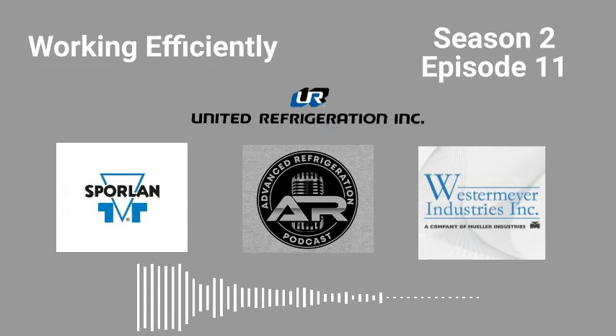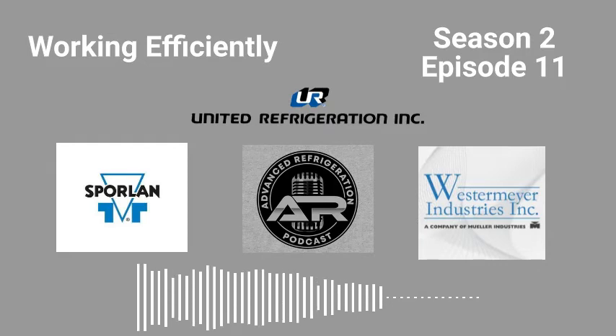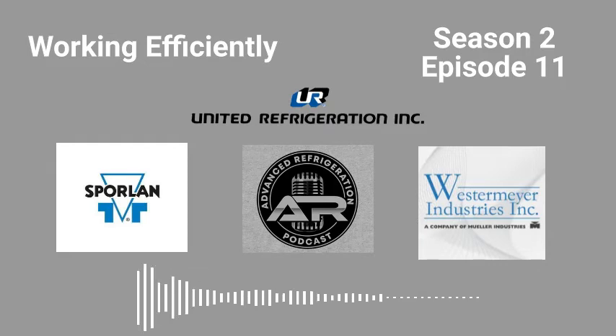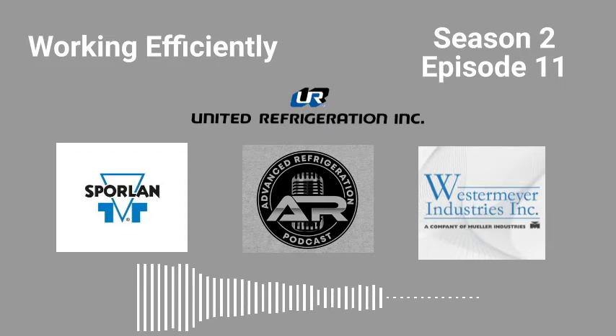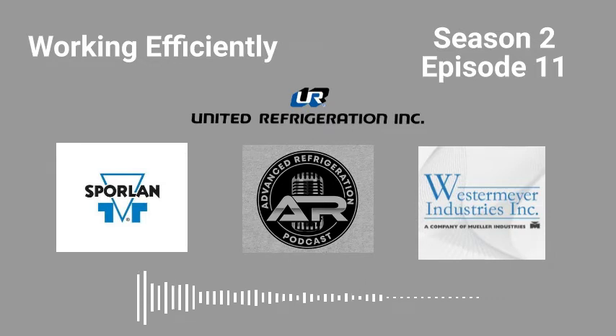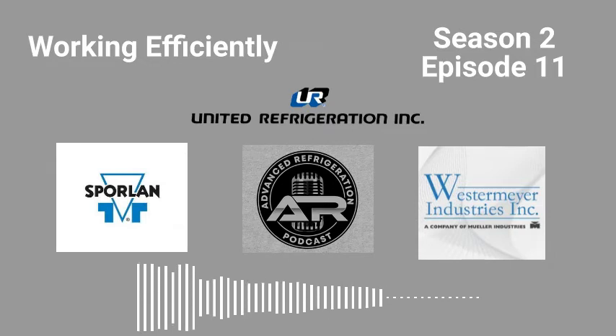Or, for example, we did a rack the other day that had a 5/8 flare fitting on the receiver — all of them do, on the receiver and the suction header. Nobody uses it because they don't have an adapter, but in my kit I've got a 5/8 to 1/2 inch adapter. So now I'm flying — pulling all the gas out in half the time of someone using a 3/8 tap on the back of the rack.